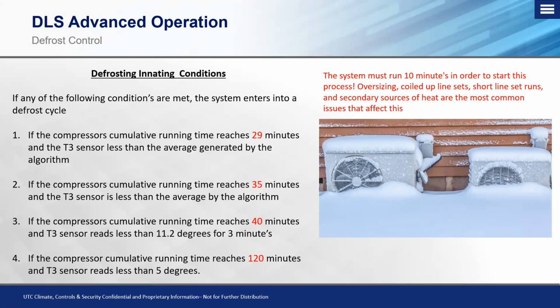Okay, ductless systems should be designed to handle the full load. It is not recommended that these be put in, especially for heating circumstances, as a secondary source, just because they require a certain amount of runtime to start looking at different control algorithms for defrost, which you can see on the left, which we'll get into in a minute.